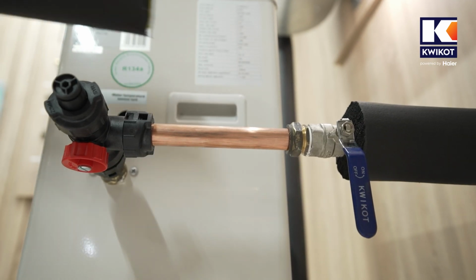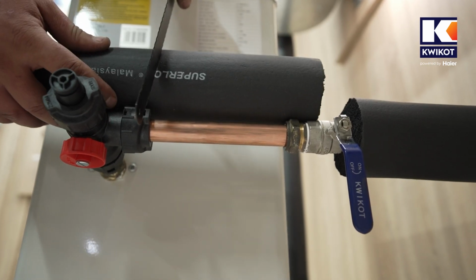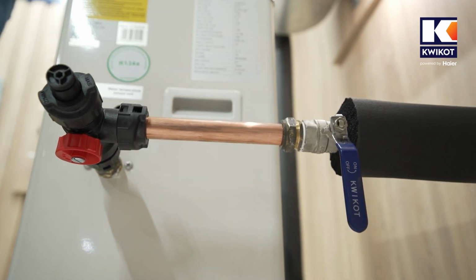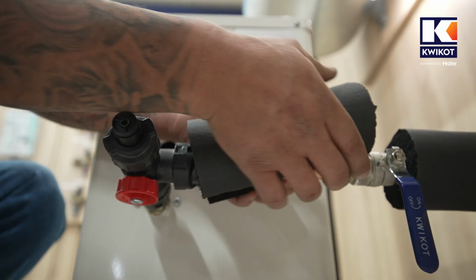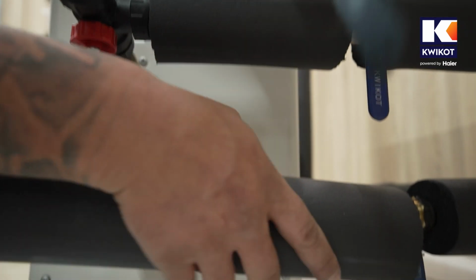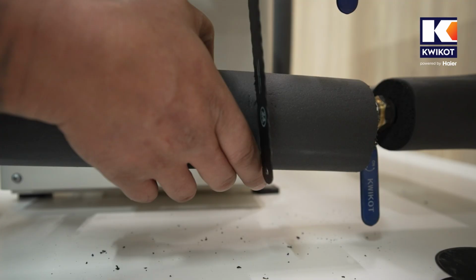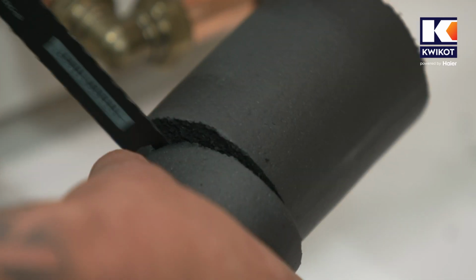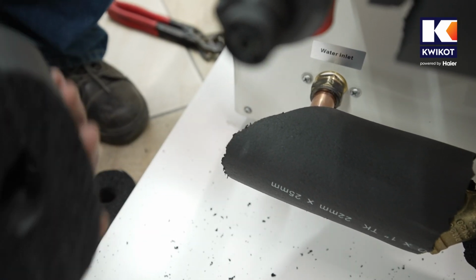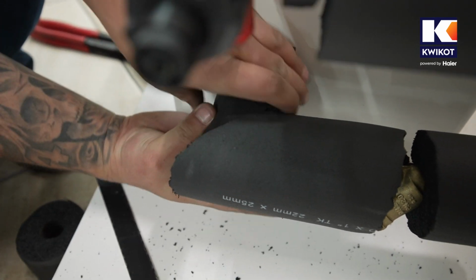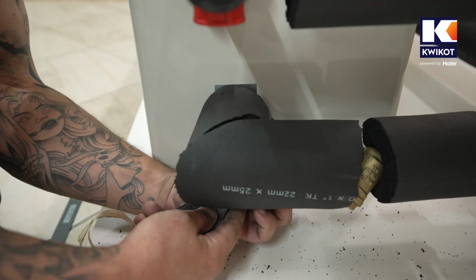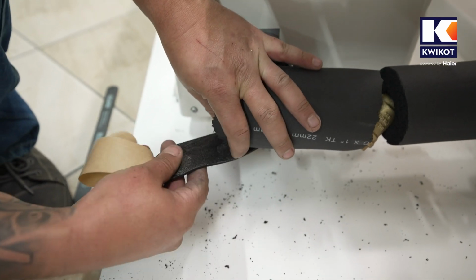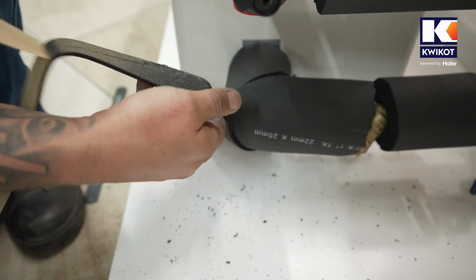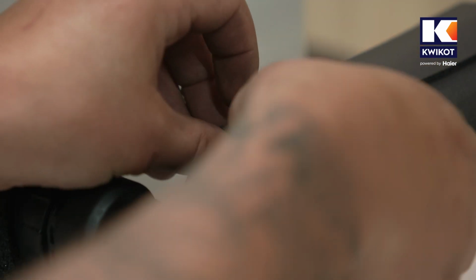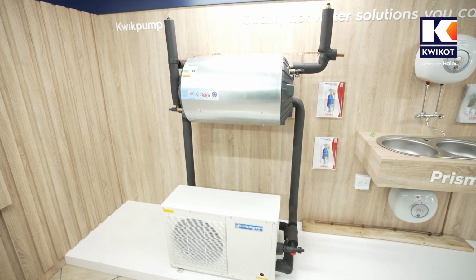And lastly, we apply some lagging to the short section between the mixing valve and the ball valve, and another piece around the first length of pipe between the heat pump inlet and the lever ball valve. And tape up the gaps in the lagging. So now our pipework is done.